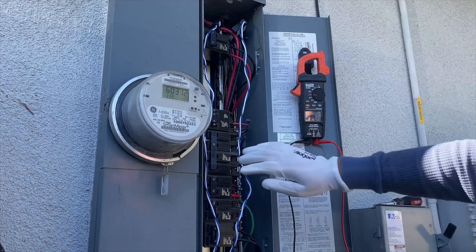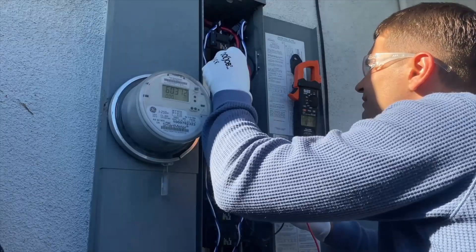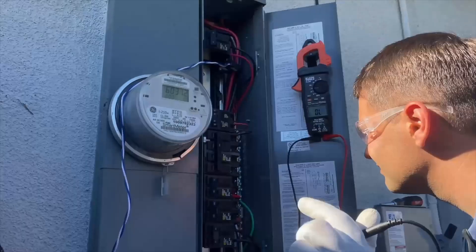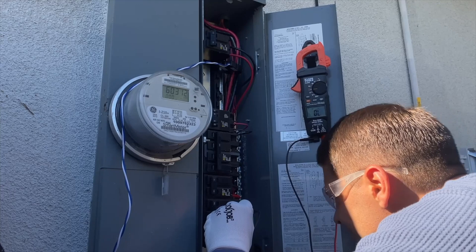Now I'm going to follow another Enphase recommendation, which is to route all wires from the circuit breakers through CT sensors — to the top and to the bottom. First we have to identify all leg 1 wires and all leg 2 wires, so we're going to have one L1 and one L2 CT sensor on the top and two sensors at the bottom.